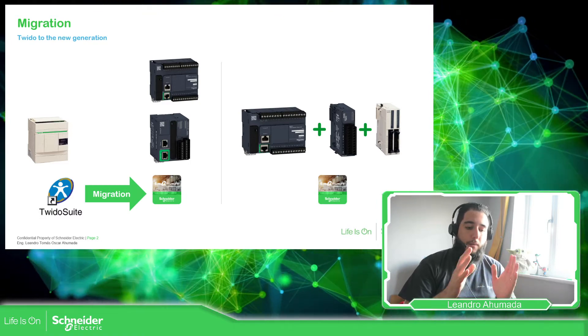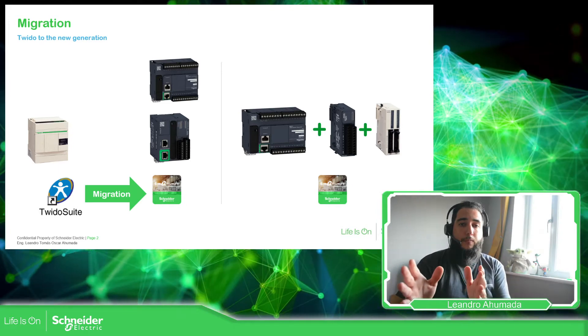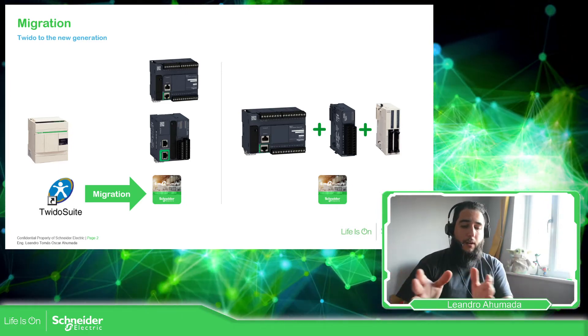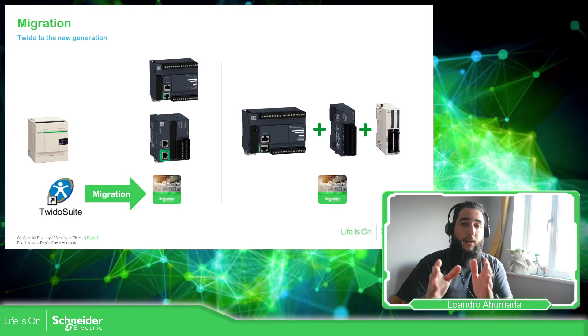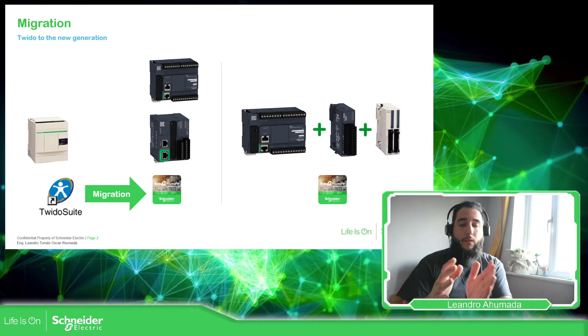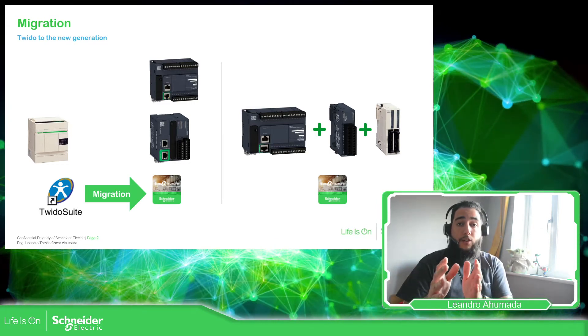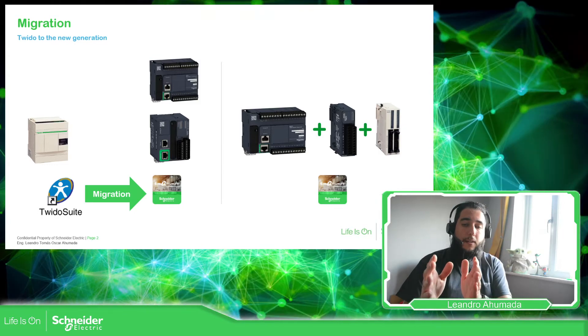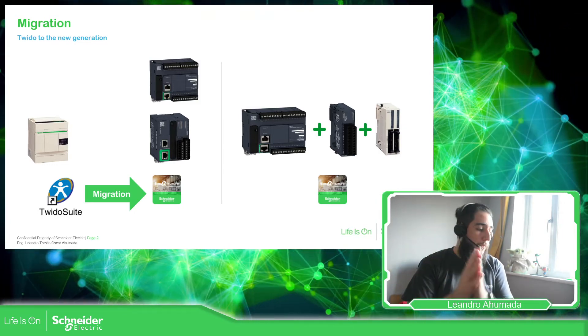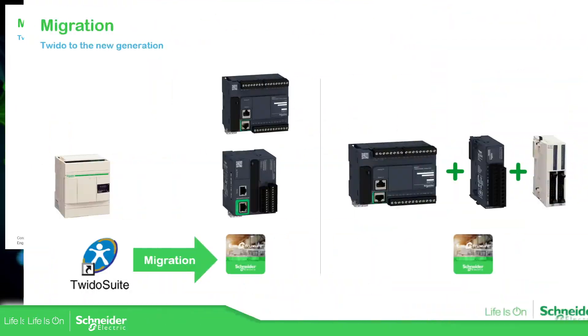If you are using Twido with expansion modules and you migrate the application to the new software, the software will ask whether you want to retain those expansion modules or convert them to the new TM3 family range — instead of TM2, they become TM3. Let me show you an example.